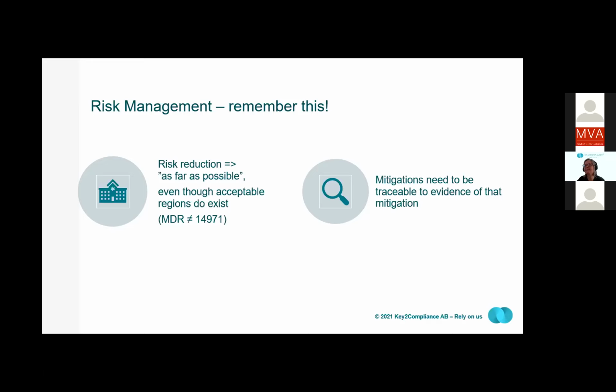Risks should be identified during the normal intended use and reasonably foreseeable misuse, and also if risks would arise from the mitigations themselves. This is something that is often forgotten in the risk analysis. Mitigations of a risk also need to be traceable to evidence of that mitigation. The priority of reducing risks is not changed since MDD, so the manufacturer needs to eliminate or reduce risks as far as possible through safe design and manufacture in the first instance, and secondly, take adequate protection measures, and lastly, provide information for safety and train users. And somewhere in the risk management file, the competence of the team needs to be explained, and that all different competence and experience is covered in the team, including experience from using the device.